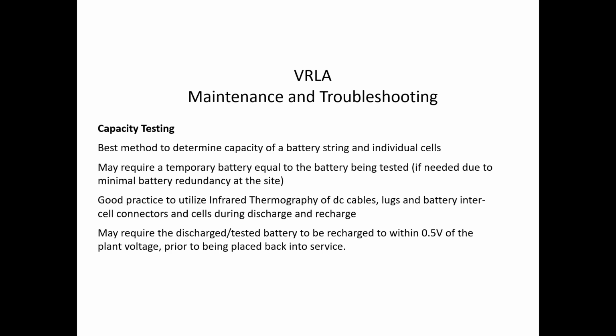if it's a single string application and you have a weak or a bad cell and a cell opens up, it's a chained weakest link theory. That thing opens up, you'll drop your load. You won't have time to respond. Anyway, there's a few reasons why we recommend an actual full load test.